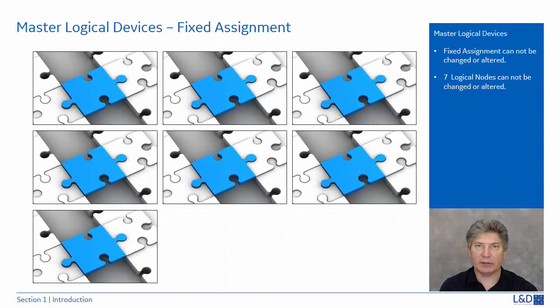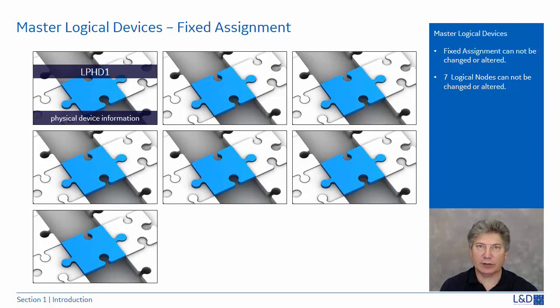Next, let's focus on the master logical device. The master logical device has seven logical nodes associated with it that are a fixed assignment and cannot be altered. Let's review the seven logical nodes and what they are. The first one is the LPHD1, which contains the physical device info such as the vendor, software revision, serial number, model number, relay name, physical location such as latitude, longitude, and altitude, and if there are any other errors.